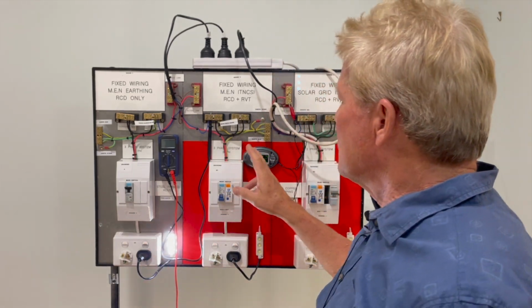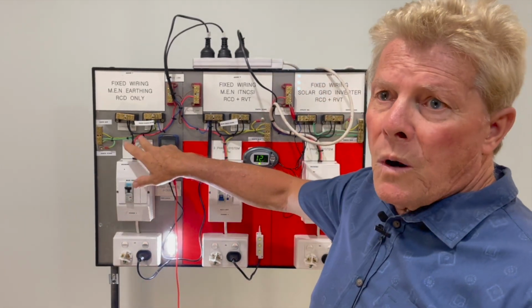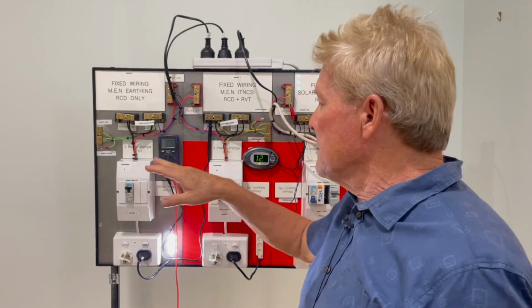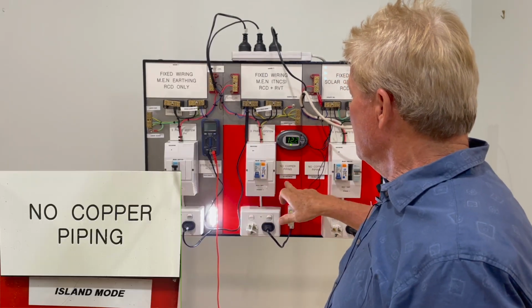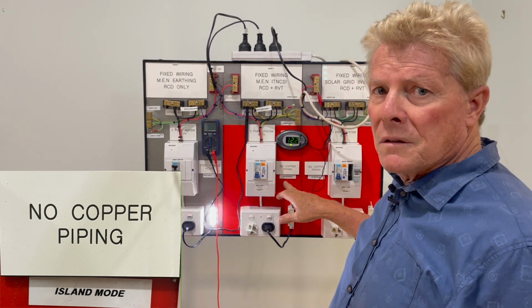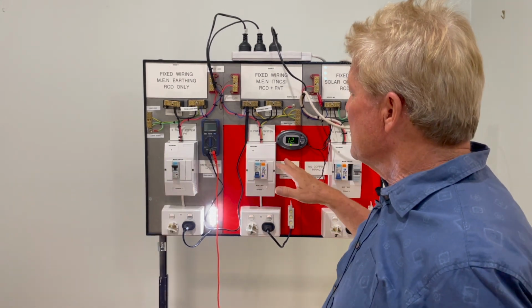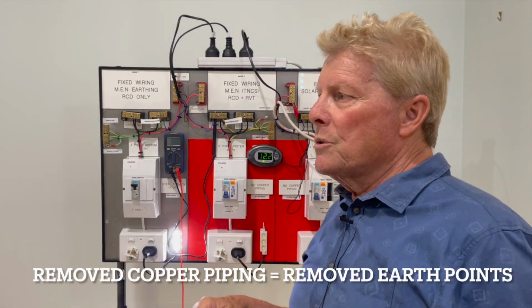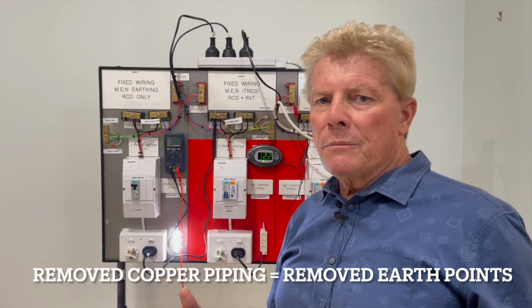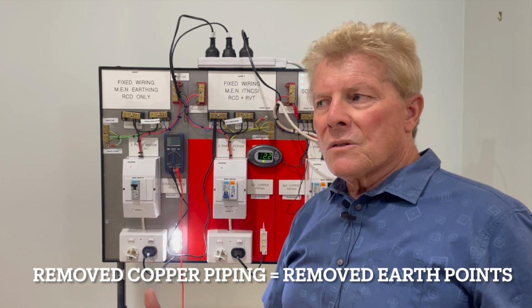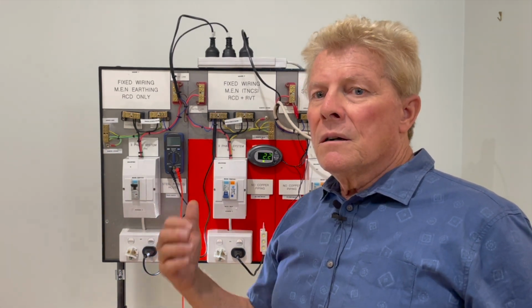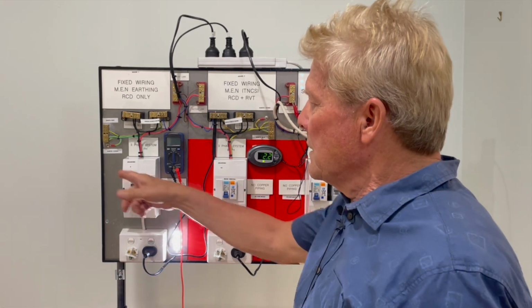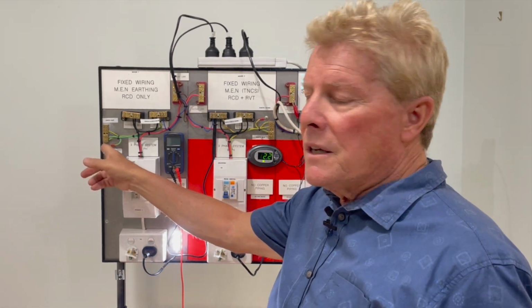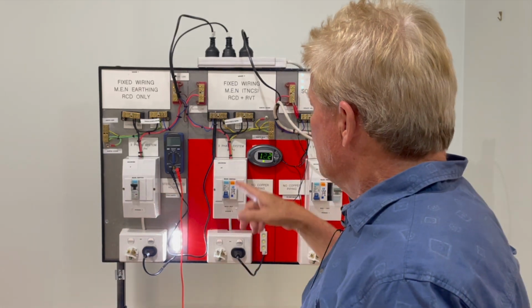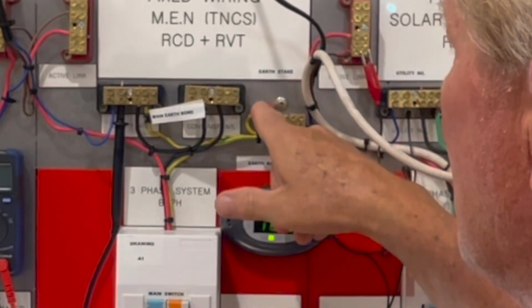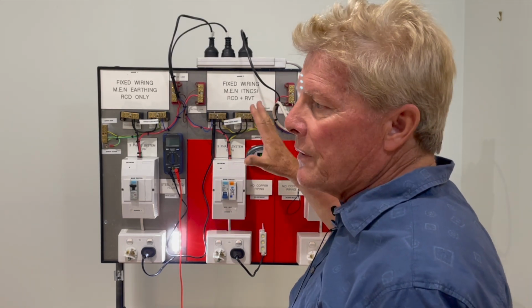And this is house two. So house one is on A phase. House two is island mode. There's no copper piping. So island mode just shows you how once the copper piping is removed, you remove a lot of your earthing points inside your system. So your MEN is no longer multiple earthing points. It's only the one, which is this one over here, your earth stake. We've got our earth stake up here in house two. That's it represented up there.